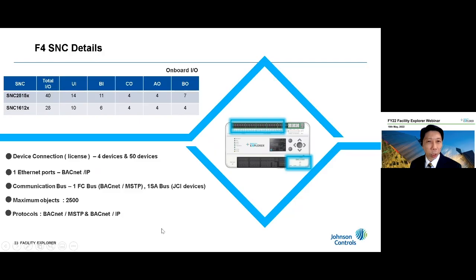This SNC is designed with one Ethernet port that allows connection to BACnet IP, and one FC port and one SA bus port that will connect MSTP and JCI devices on the SA bus. Inside the box, we have about 2,500 objects available for programming, including all the BACnet object points and software points, which is the maximum capacity. The supported protocols include BACnet IP and MSTP at this time. So next.